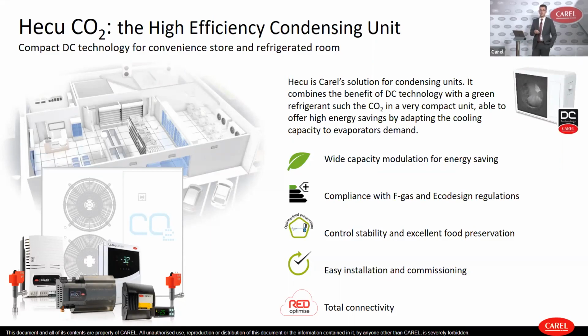It has an additional fine-tune of the working conditions of the unit in accordance to what the cabinets, the users, are requiring in real time. So in this way, we can improve the efficiency and the operating condition of the unit, but at the same time, we can keep the temperature inside the cabinets very, very stable. And that means that the food can last longer in the cabinets, and the customers have more time to bring this food. And of course, the end users, the retailers in the supermarket, have more time for selling the food. This solution is completed by some tools for an easy installation and configuring, and of course our remote supervisory and remote services for the total connectivity by remote of these units.